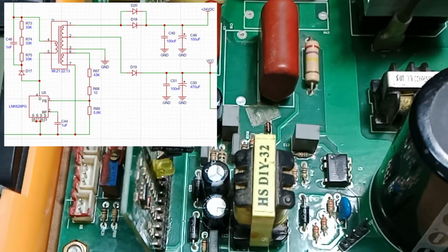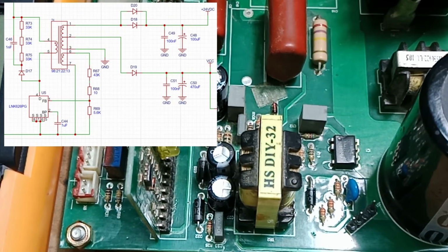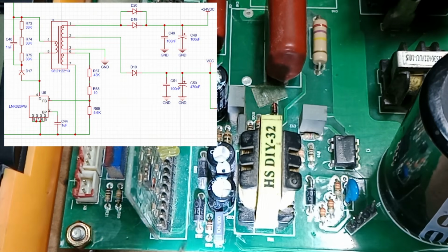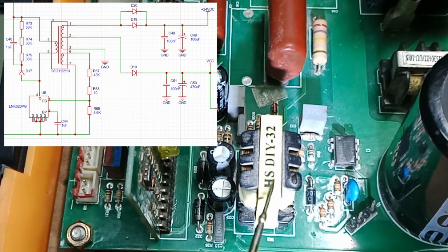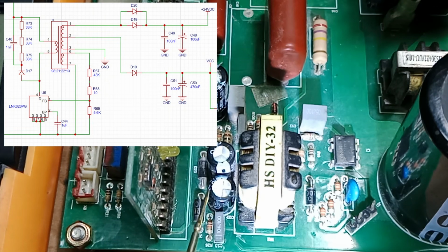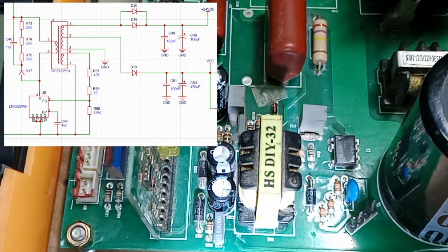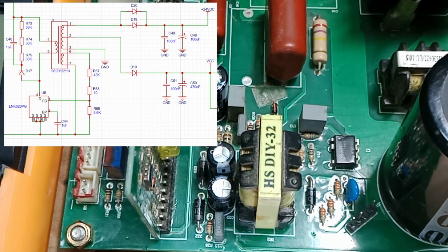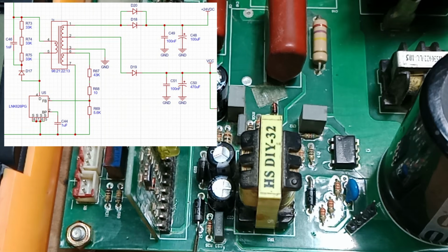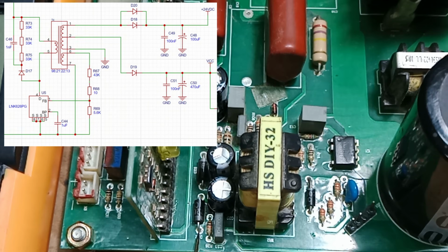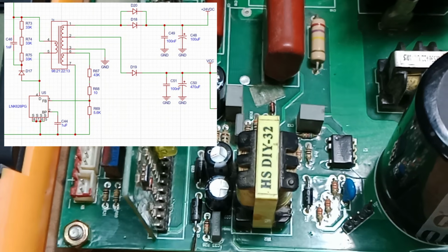The auxiliary power supply produces the low voltage DC supply to the PWM controller, the fan, and the relay. It has this switching power supply section and this step-down transformer. Near the transformer, there are rectifier diodes and filter electrolytic capacitors. We can check the DC output of the auxiliary power supply at the pins of the rectifier diodes.